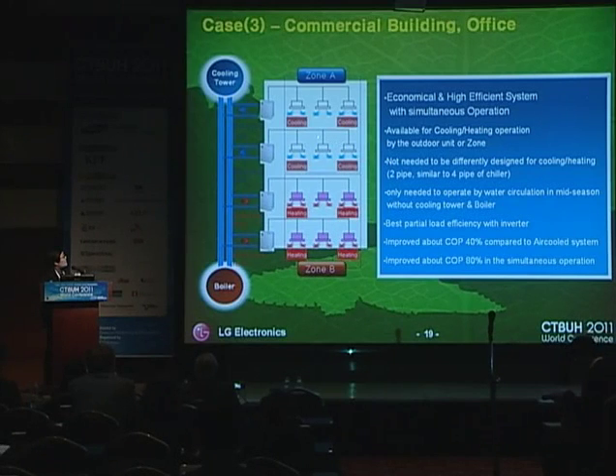A water-cooled heat pump system makes heat using a cooling tower and a boiler. When this building wants cooling, it must operate the cooling tower, and when it wants heating, it operates the boiler. But in the building, there are heating and cooling loads at the same time. This building does not operate the cooling tower and boiler, just circulates, and then heats and cools at the same time. So this building's energy saving effect is very high.